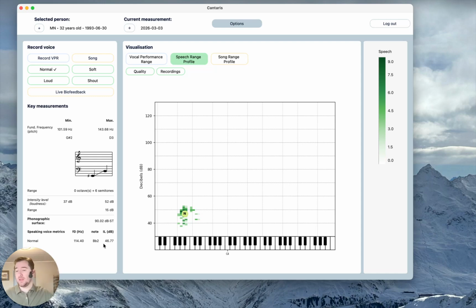Now, older people and more women than men tend to speak a little bit softer than that, and younger people, a little bit more men than women, tend to go above that 60 or maybe 70 decibel point when you measure at 30 centimeters. Now, at this moment this is not going to make a lot of sense because I made this kind of sham calibration, but that is what you'll probably see. Now, if you've calibrated right and you make this kind of measurement and it's something like 100 decibels or 35, then something went quite wrong, probably. I don't think that's gonna happen, but if it does, just reach out to us. We're quite accessible. Maybe we can fix that at a distance with a video call, for example.